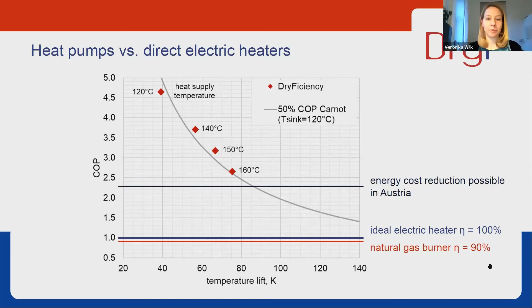I'm already at the end of my presentation, and I have put here some important aspects. We have successfully commissioned the DryFiciency heat pump at Wienerberger. We reached 160 degrees C, which was basically one important part of the project, to show that those high heat supply temperatures are possible. We are very happy about the COP values that we have reached, and this also translates into significant CO2 and energy cost reductions compared to natural gas.